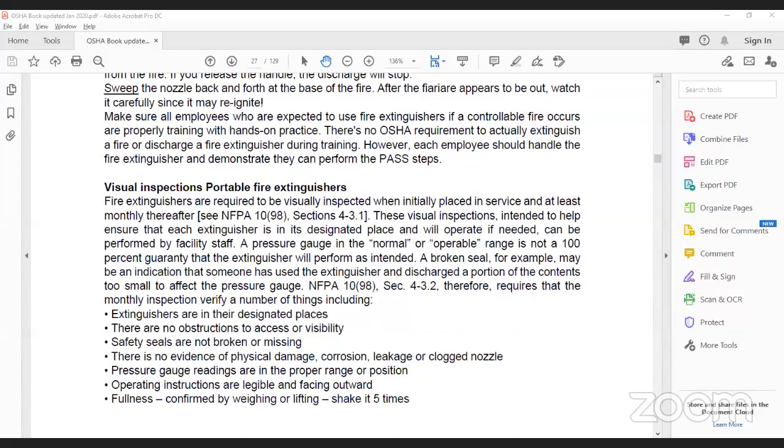Because it happened to me in my experience. We bought once, although it's not a fire extinguisher, a oxygen cylinder, and when I was installing that oxygen cylinder, during the leakage test there was a leak on the valve seal. So I immediately took it out and complained to the Air Liquide supplier where I got the cylinder from, and they replaced it for me free. So there are some cases like that. Any other guy who can tell me why we need to shake 5 times?